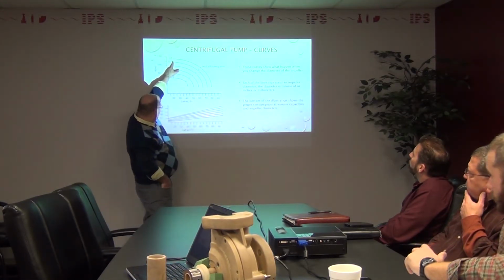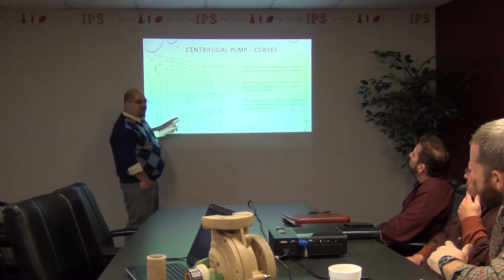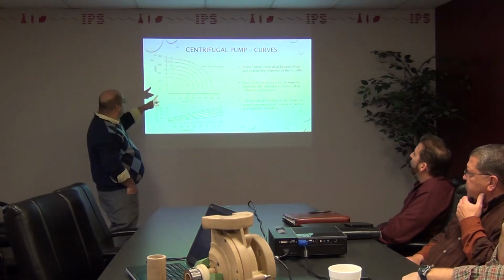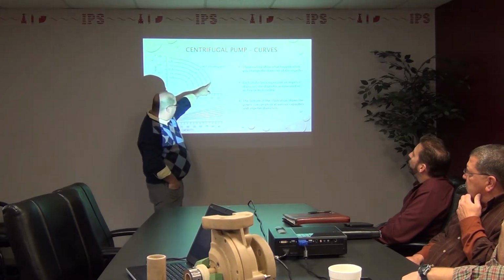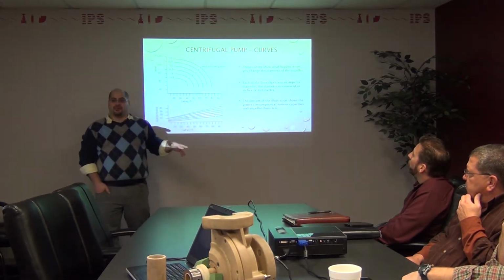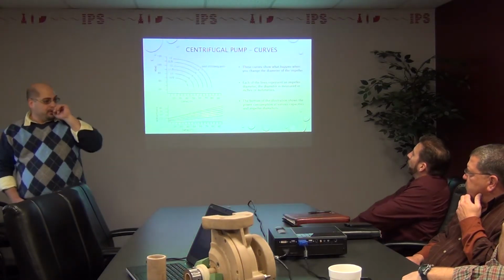Before, when I was operating here, I had this 15 horsepower motor, not a problem. But when I'm operating out here, oh boy, I need a 40 horsepower motor. And that motor is burning out, tripping, and failing.